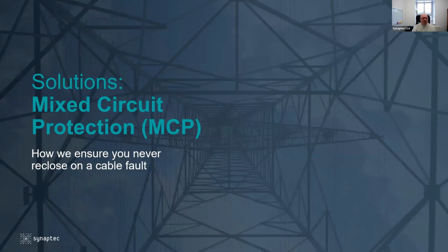So with that concept in mind, we'll show you how it's applied here in two steps. We wanted to talk about the challenge of protecting complex circuits like mixed circuits that combine overhead and underground cable sections, which is increasingly prevalent in a lot of high voltage and medium voltage grids around the world. And this is all about ensuring that you never reclose on a cable section fault, which causes a lot of damage and increases the cost of an outage at the very least.